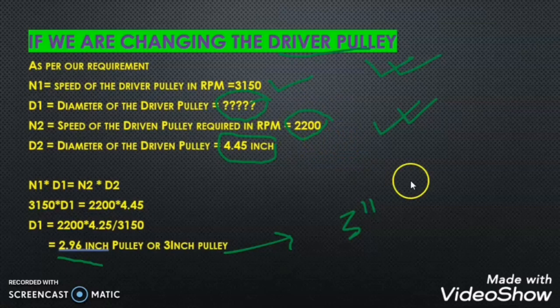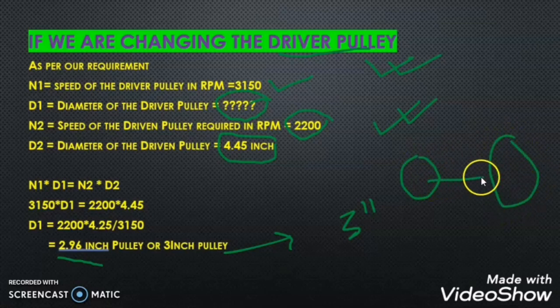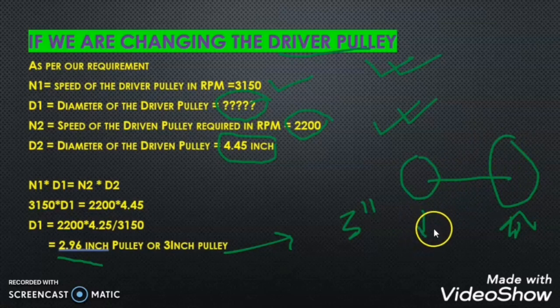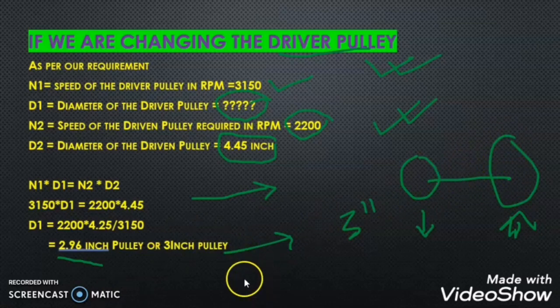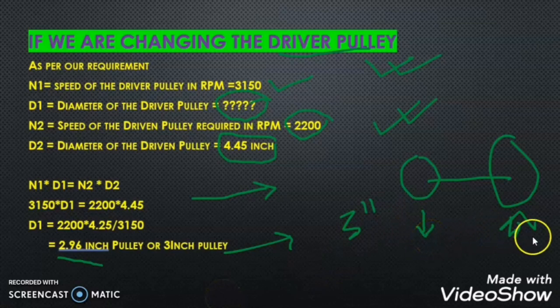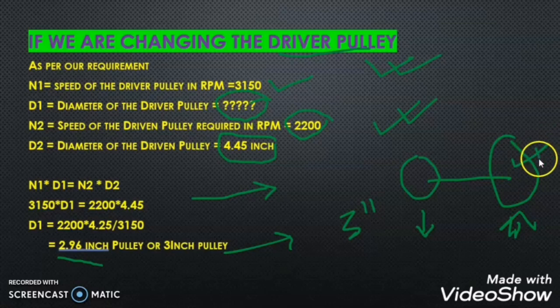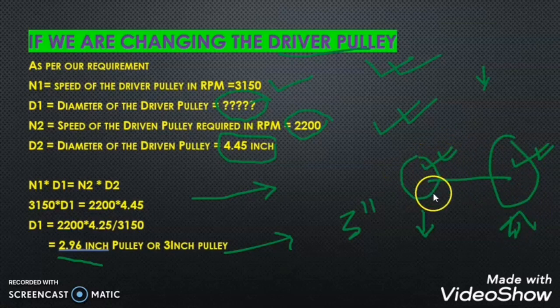Here is an important point: to reduce the speed of a load connected via pulley, if someone asks whether to increase or decrease the pulley size, your counter question should be which side pulley are you planning to change — the driver or the driven? If changing the driven pulley, you need a bigger size. If changing the driver pulley, you need to reduce the driver pulley size.